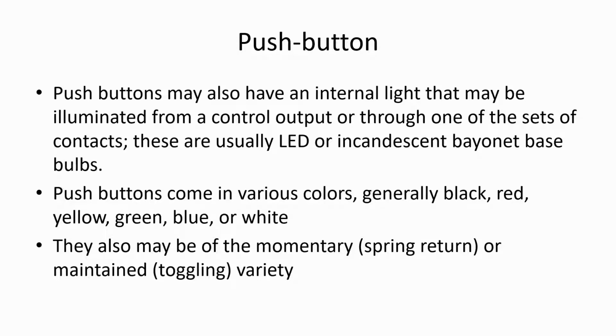There are two types of push button switches. One is momentary and another one is maintained. In a momentary or spring return type of push button, whenever the user presses the push button, the state of the contacts changes, and when the user removes the finger, it comes back to the previous state. So it is called a spring return or momentary type of push button.